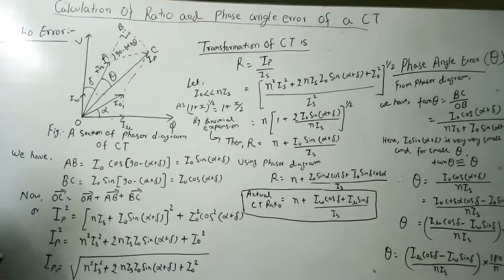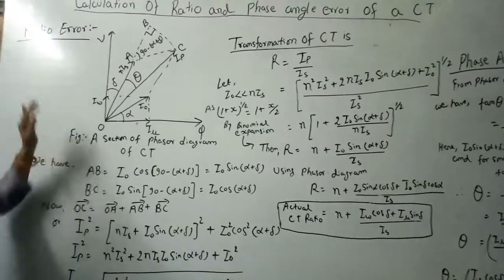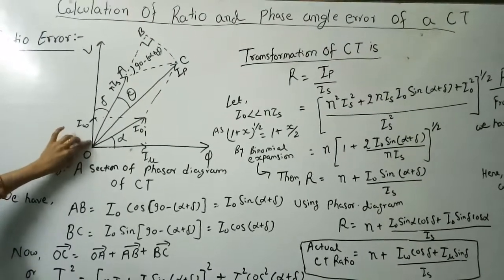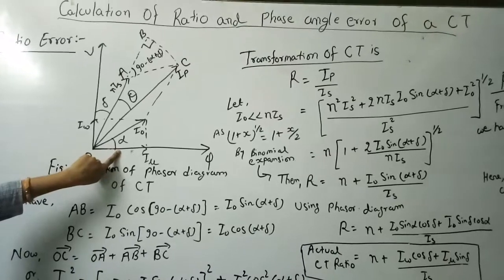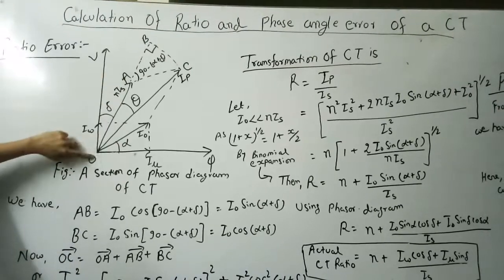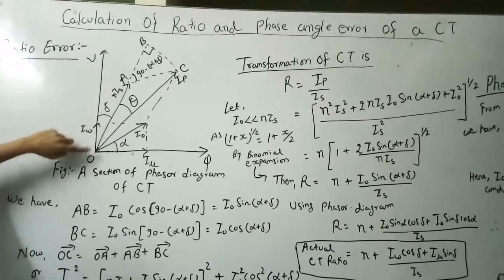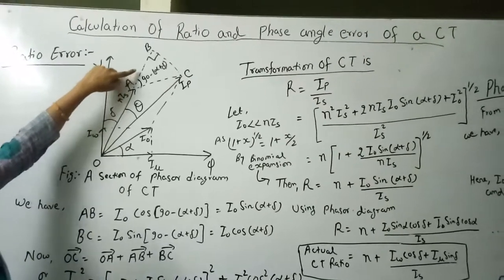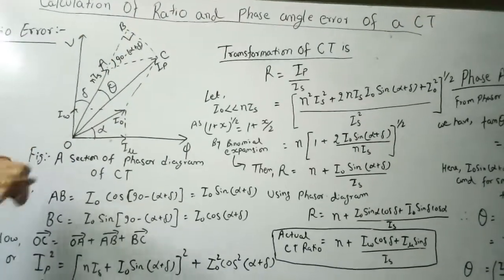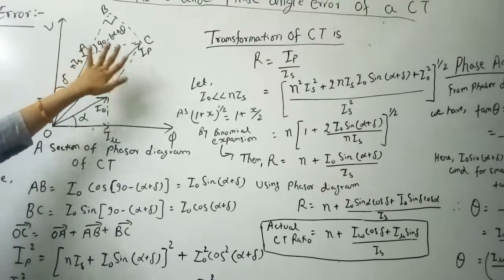Today, we will derive the expressions for ratio error and phase angle error. Here is the phasor diagram of the CT — this is the first half of the phasor diagram. We see that OA is N·IS, which is the secondary current referred to the primary side. We extend this line to AB and draw a perpendicular from C to B.